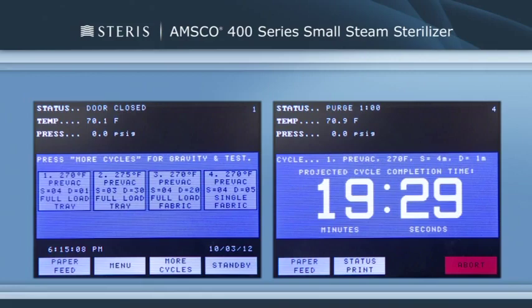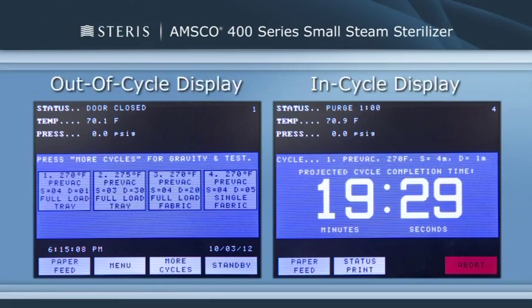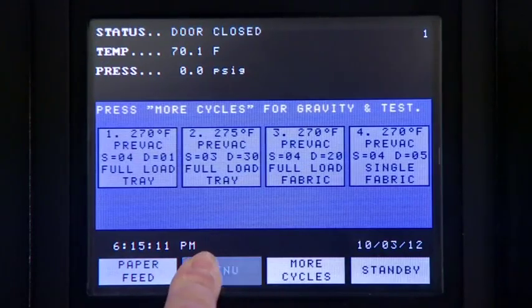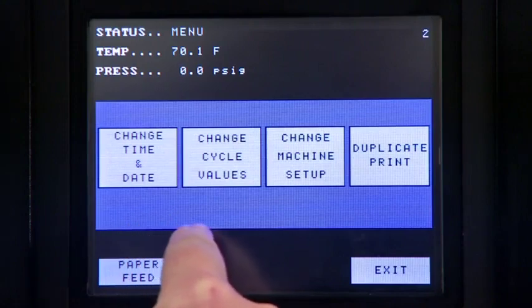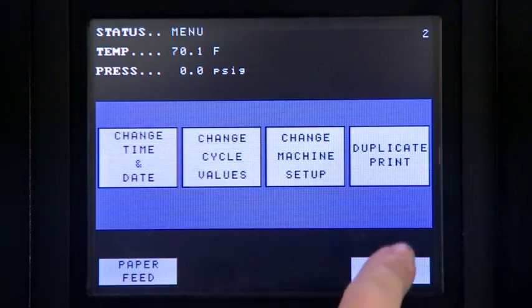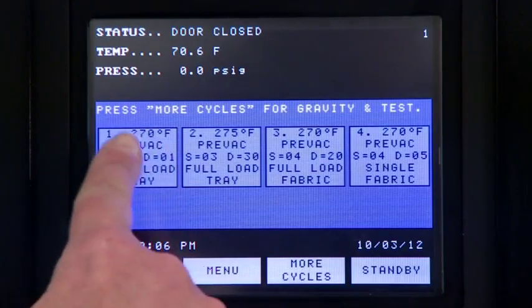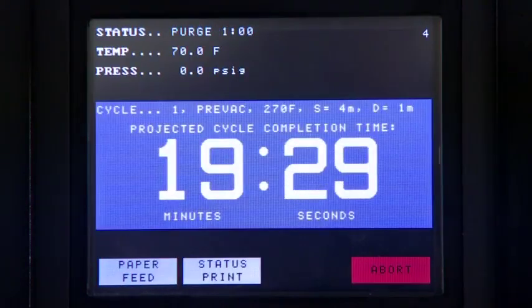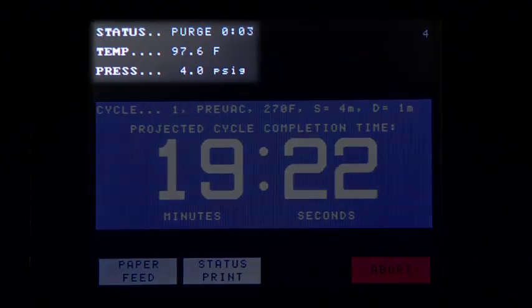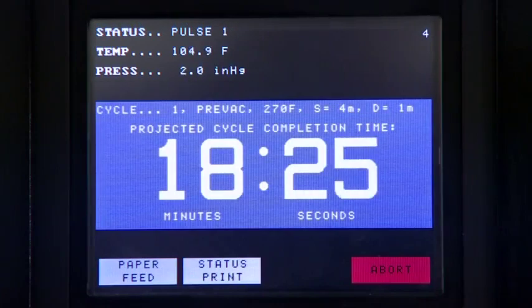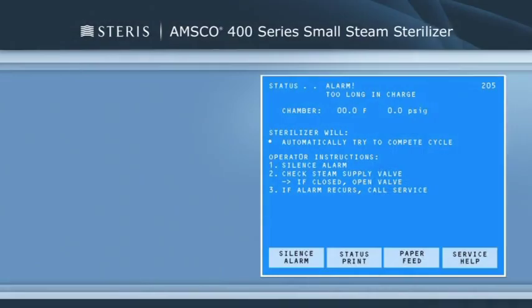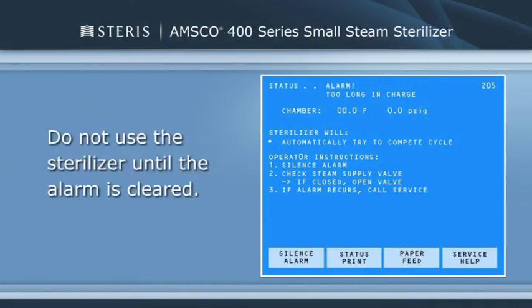Now, let's cover the control displays, which can be divided into two categories: those occurring when the sterilizer is out of cycle and those occurring when it is in cycle. Out-of-cycle displays are used to start cycles or set up and adjust sterilizer operation. With the exception of the cycle starting displays, most out-of-cycle displays will only be used occasionally. When the sterilizer is in cycle, displays generally appear automatically, and unless an abnormal condition occurs, require no special attention or instructions. In-cycle displays tell the operator at what temperature and pressure the sterilizer chamber is operating, show the current cycle phase, and indicate when the cycle is complete. When the operator is experiencing an abnormal condition, an alarm display will appear. When an alarm occurs during cycle operation, a display appears on the screen, along with an audible tone.